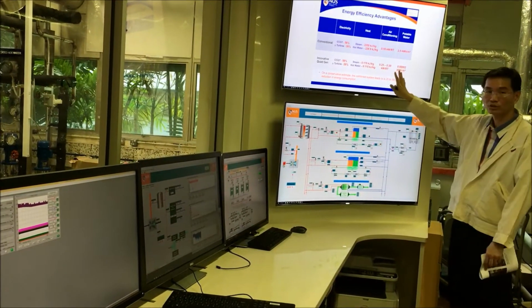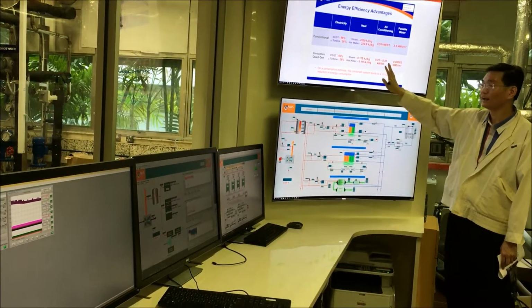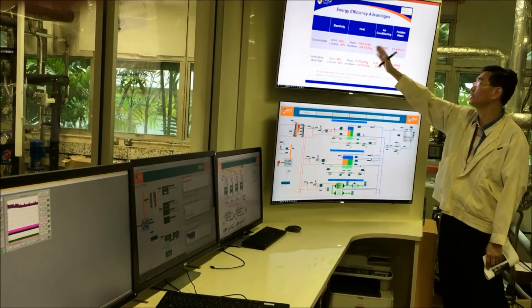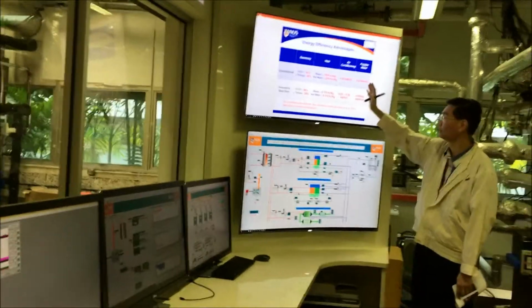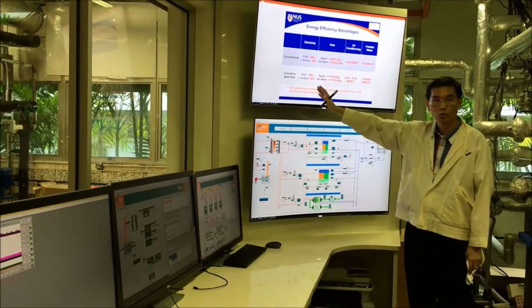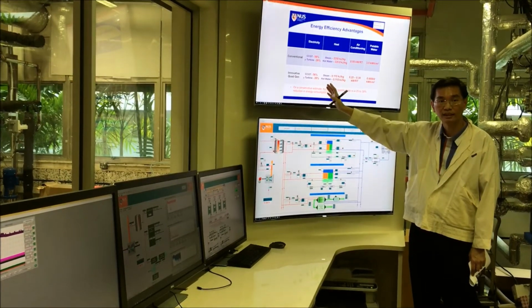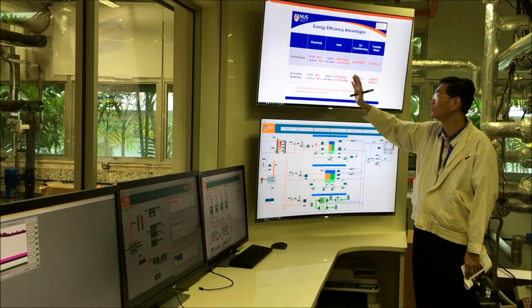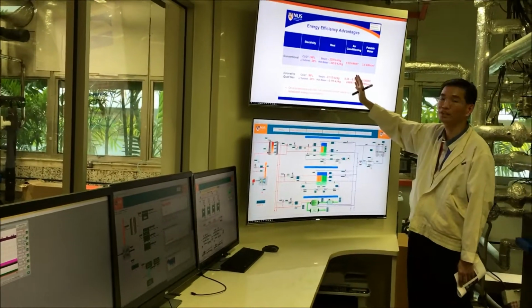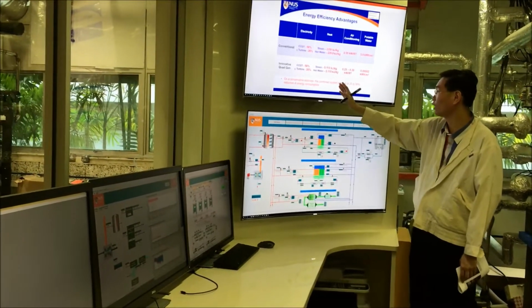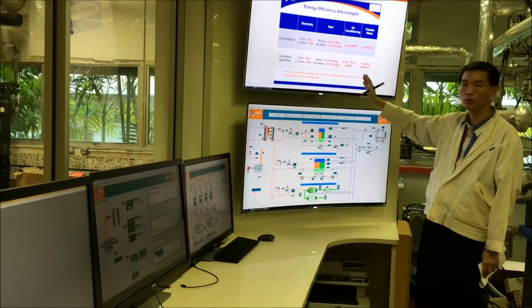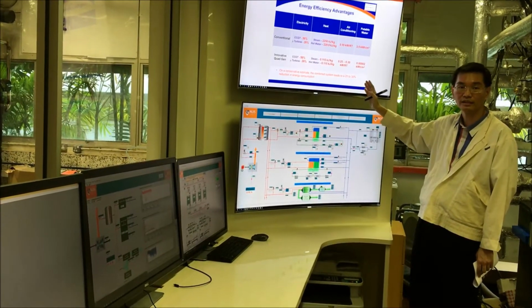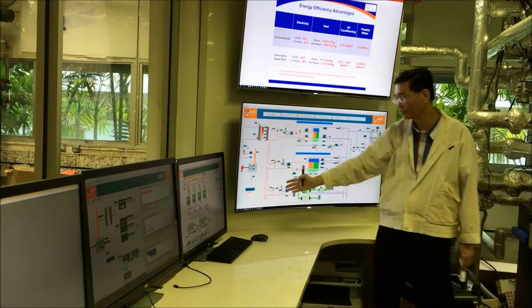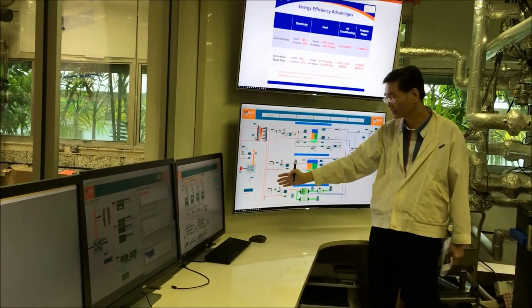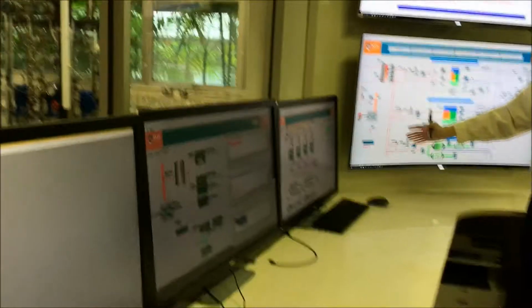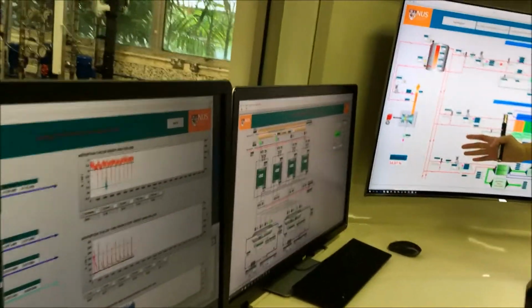So if you look at the last portion of this presentation, if you compare the conventional way of producing electricity, heat, air conditioning, and potable water, right? Using the quad-gen system, which harvests the waste heat, the innovative way of harvesting the waste heat to produce heat, air conditioning, which is in terms of chilled water, and potable drinking water, our system easily enjoys at least 25 or more than 30% improvement in terms of energy efficiency, as you can see from this screen here, which compares the performance of the plant efficiency in real time, right?